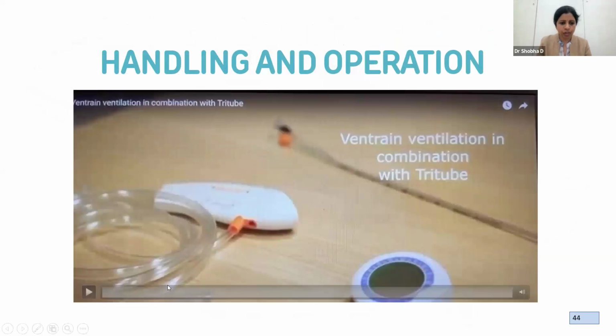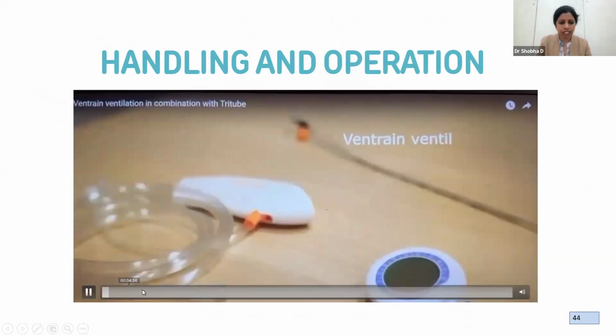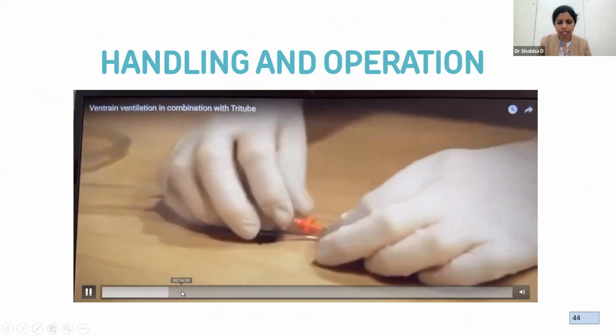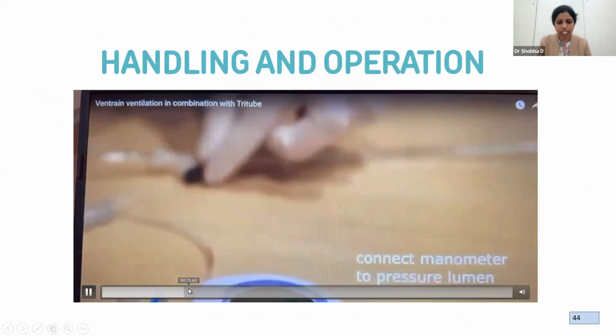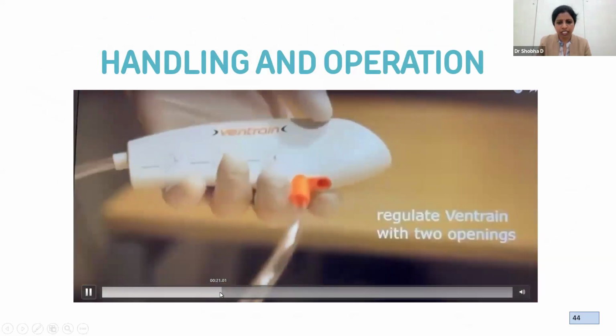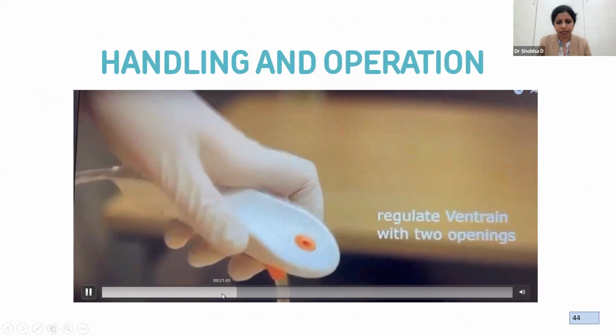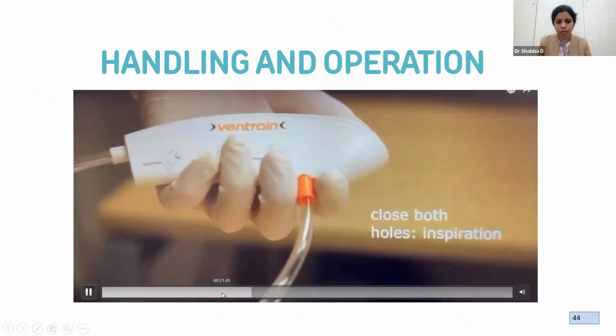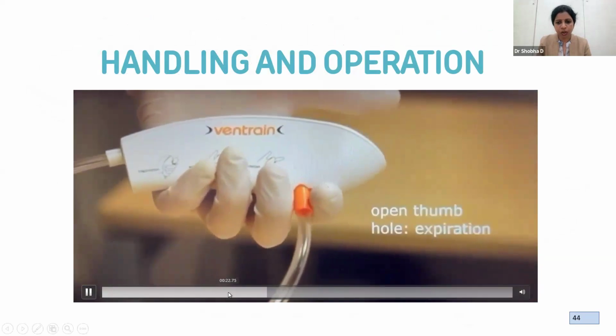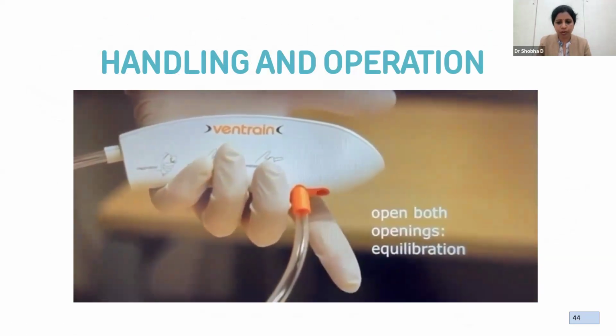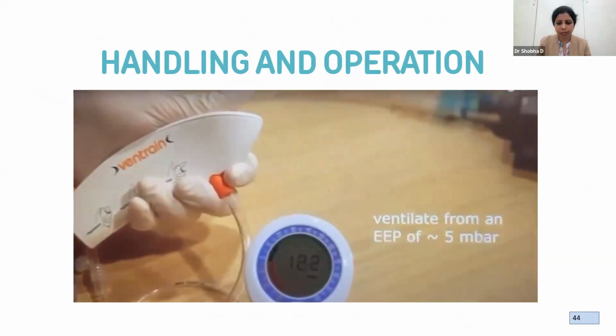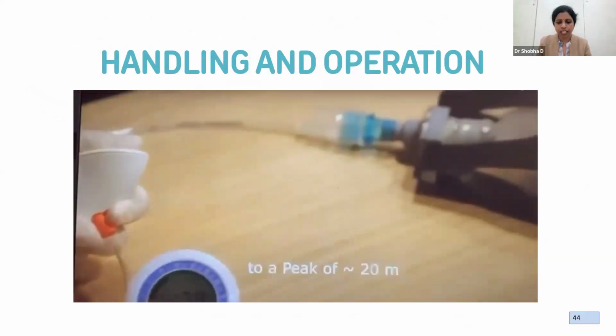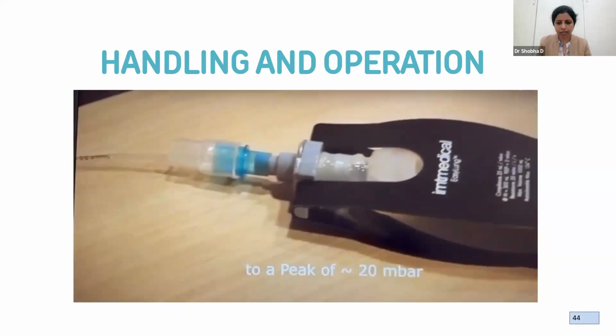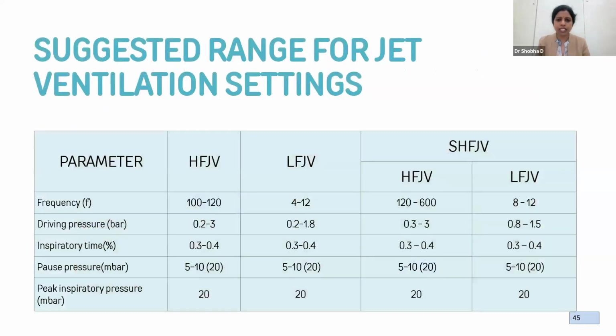So again, a small clipping on the membrane. You're going to basically connect it to the test lung and to the pressure monitoring. It has two openings. When you close both, it causes an inspiration. Opening the thumb causes expiration, and when both are opened, it causes the equilibration. So you can adjust the pressure accordingly. These are some of the settings for the low frequency jet ventilation and the superimposed high frequency jet ventilation.